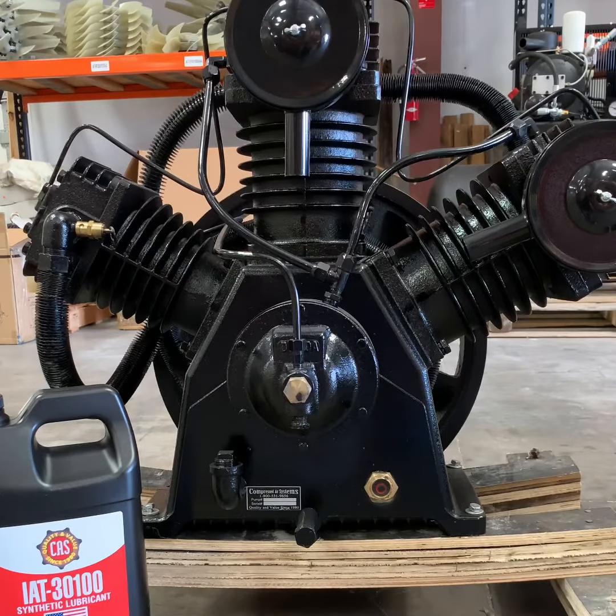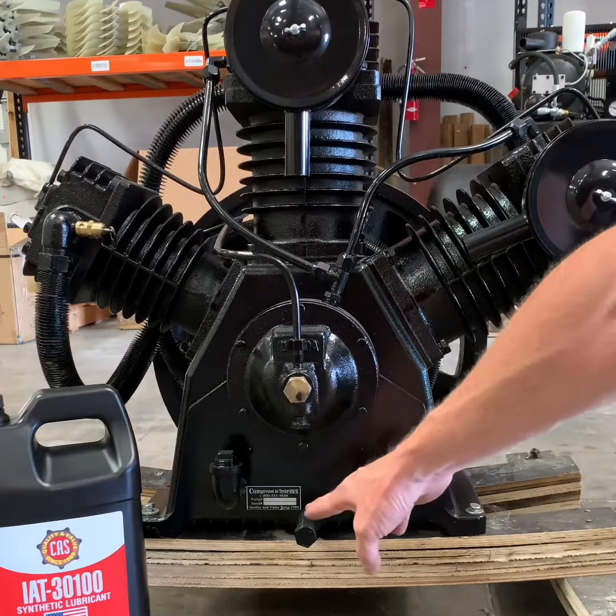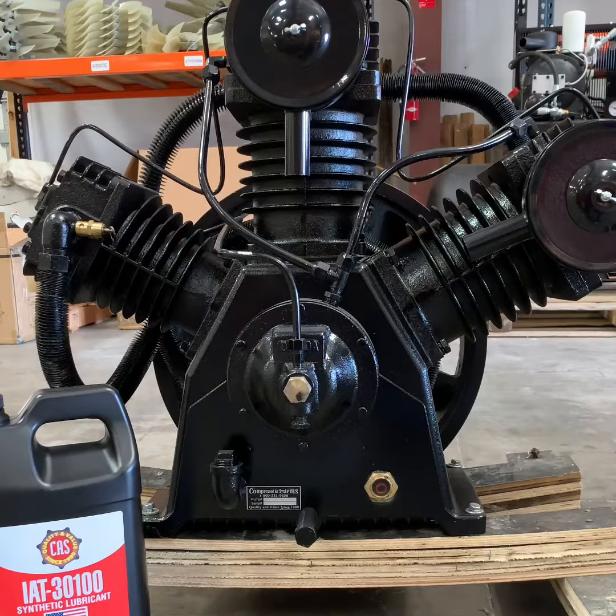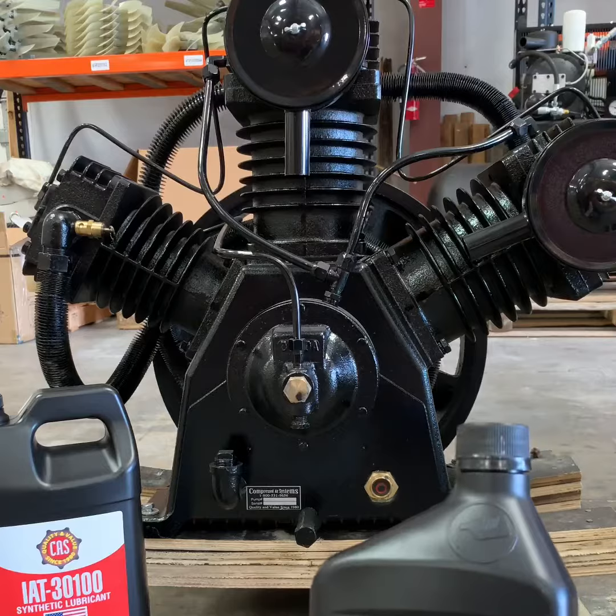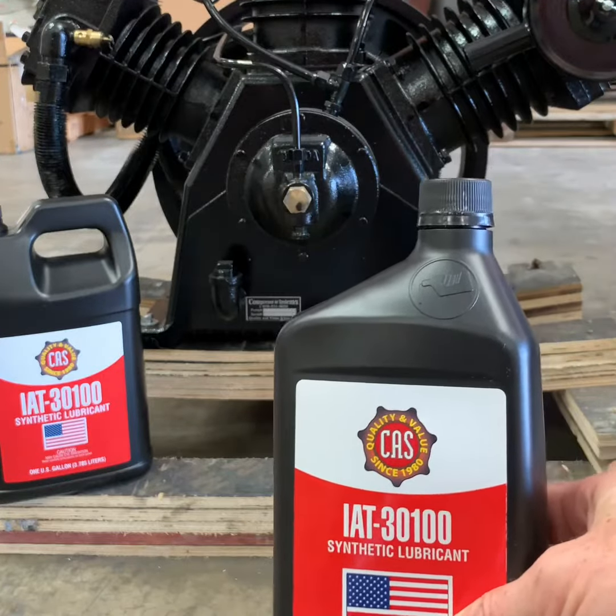In this video we are going over the CA3 series compressor pump. It includes a centrifugal unloader, oil sight gauge, oil drain, and oil fill. The CA3 series compressor pump holds approximately 4.15 quarts or 132 ounces of fluid. Always service it with IAT-30100 premium synthetic compressor lubricant.